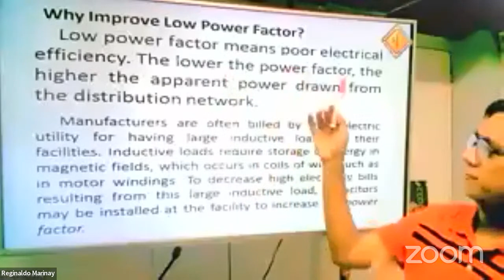We have already discussed in part 1 that the power being taken from the utility company is not real power only, and not the reactive power Q only, but it is the S, the kVA. The higher the power factor, the lower the apparent power you get. In other words, the lower the power factor, the higher the apparent power drawn from the distribution network. And that is the advantage of power factor correction.